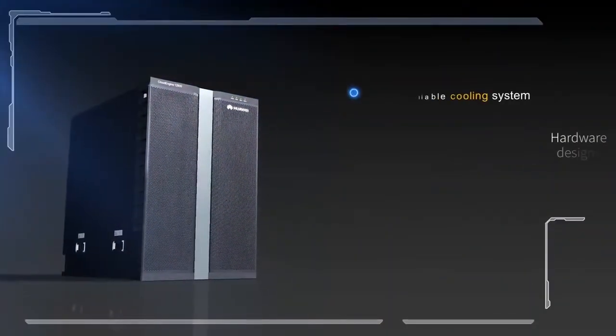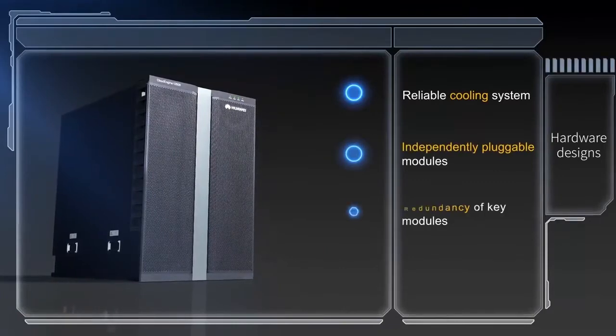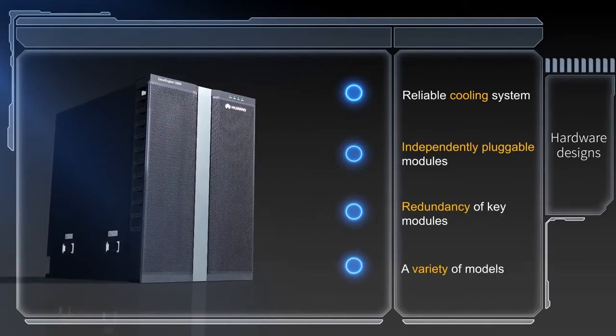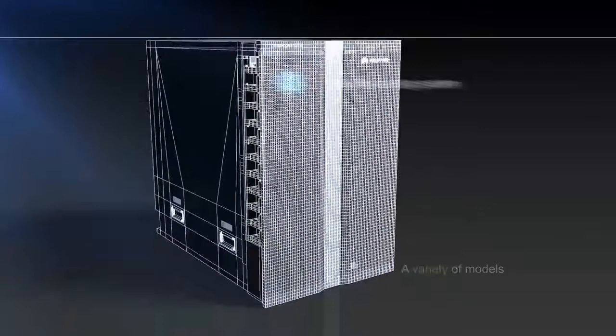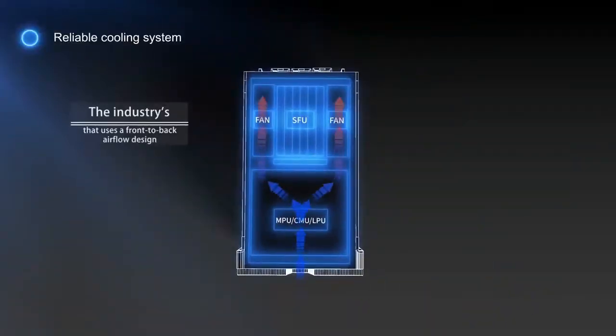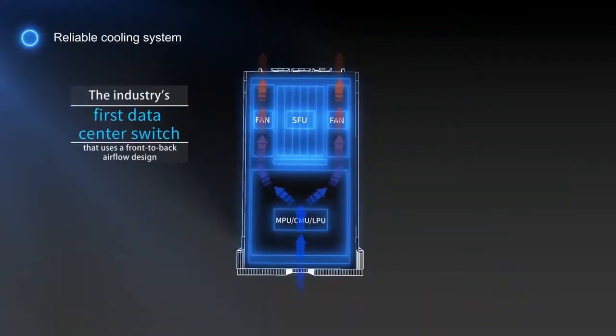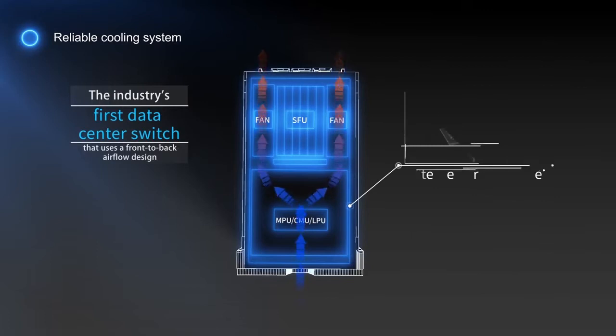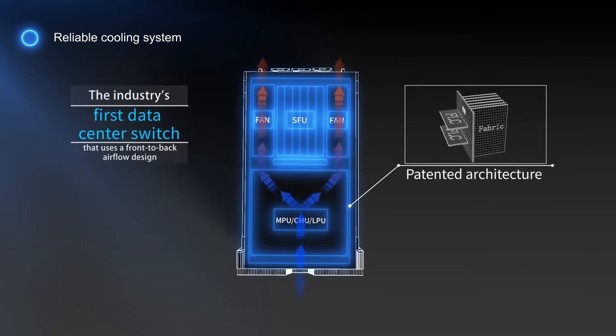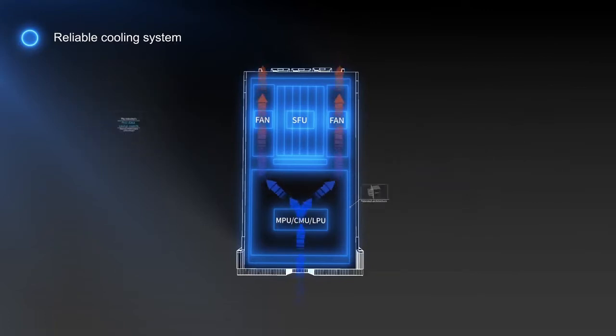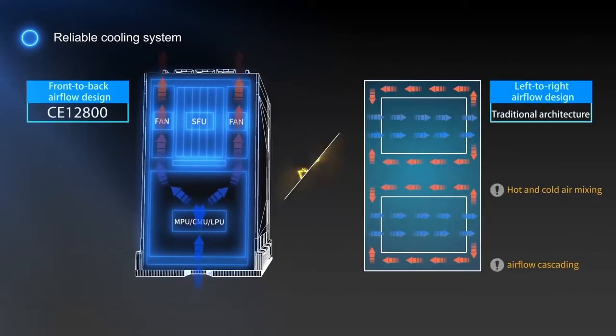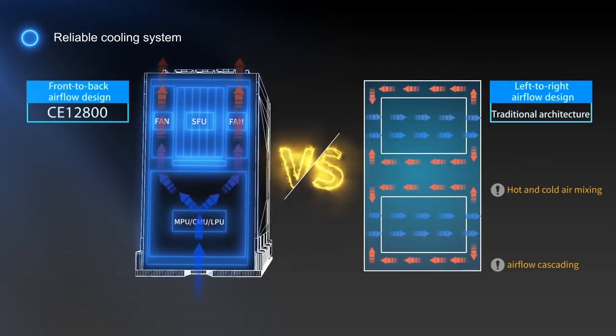Additionally, the CE12800 uses a series of industrial-grade hardware design. It is the industry's first data center switch that uses a front-to-back airflow design. This design isolates hot and cold airflows and separates cooling air channels of line cards and switch fabric units, preventing hot and cold air mixing and airflow cascading issues found in traditional architecture.